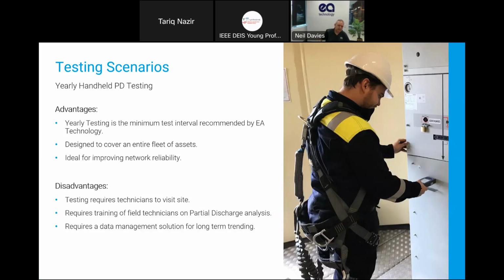The good thing about this is you can test large numbers of assets, so it doesn't take you a long time to do a spot check on a substation. In this one, we're testing a ring main unit. It might be a 15-minute test of a ring main unit, so you can do many a day. Maybe the travel in between, depending on the distance there. So it's ideal for improving network reliability, particularly if you've got a relatively poor performing network and lots of problems that need to be identified quickly, is to get it out there and test.